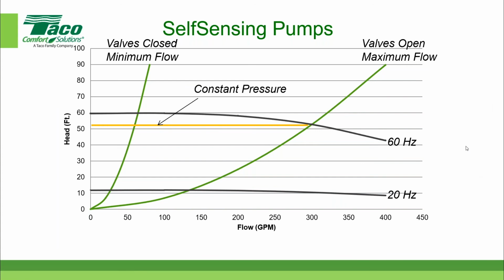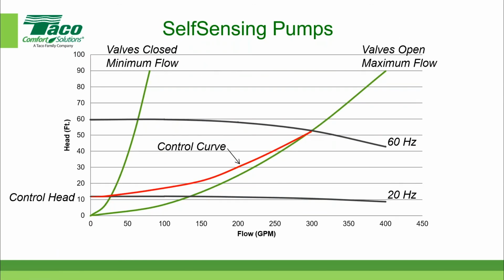But the majority of self-sensing pumps actually, let's go back here. Sorry, went in the wrong direction. The majority of self-sensing pumps are sold for this basic functionality, where you have a variable speed pump in a two-way valve system, and you're varying the speed of the pump as a function of valve position without any external control components. There's no differential pressure transmitter, there's no wiring, there's no controller, there's no control signal. It's just the pump motor drive assembly. Put it into the piping system, power it up, press the button, it knows exactly what to do. Any questions about how a self-sensing pump functions?